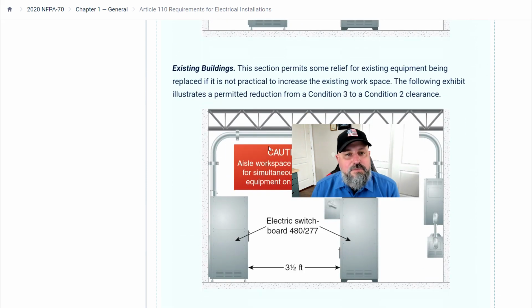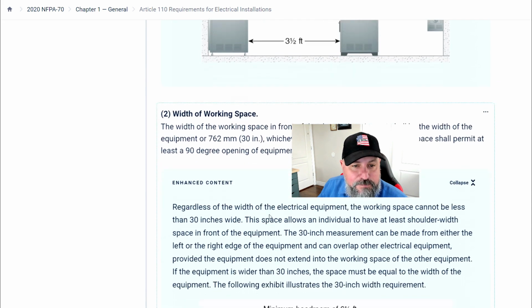Existing buildings. This section permits some relief for existing building equipment being replaced. If it is not practical to increase the existing workspace, the following exhibit illustrates a permitted reduction from a condition 3 to a condition 2 clearance. So right here, 480, aisle workspace is insufficient for simultaneous access to equipment on both sides. So you're allowed to do the condition 2, which is 3.5 feet, if it's existing, right? Okay, so that's there.